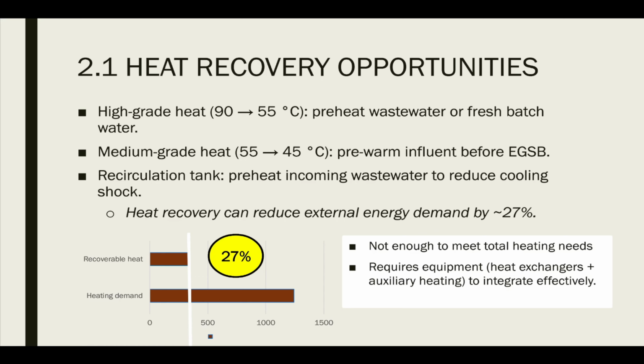However, in total, we found that heat recovery could save about 339 kilowatt hours per day, which covers around 27% of the total heat demand. So while it doesn't meet the whole demand, it still represents a meaningful saving. Thus, to actually make this work, we would need extra equipment such as heat exchangers and possibly an auxiliary heater to cover the gap. That way, we can capture this wasted heat and reduce how much external heat energy is required.